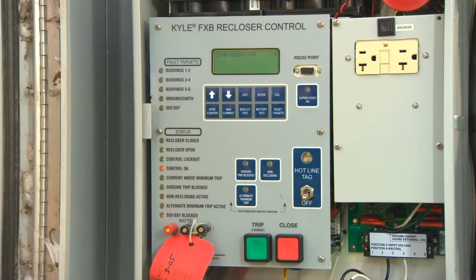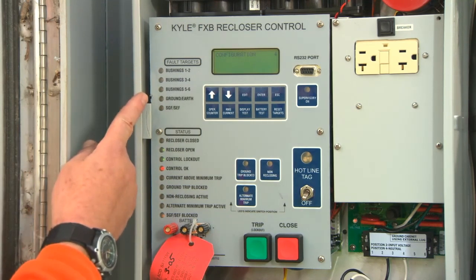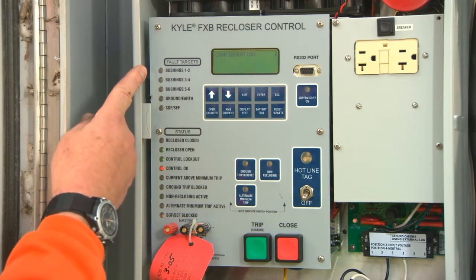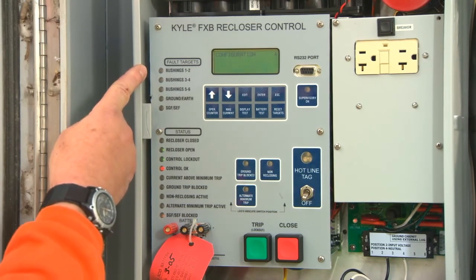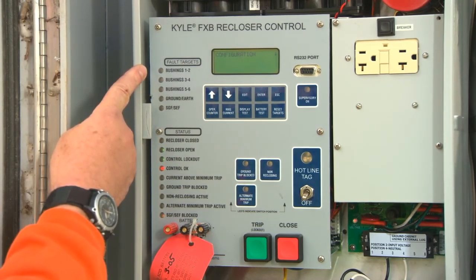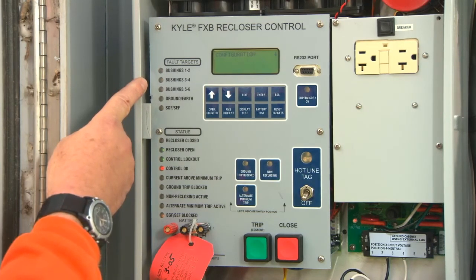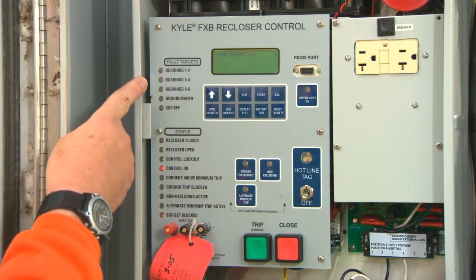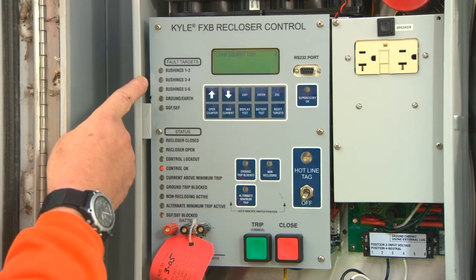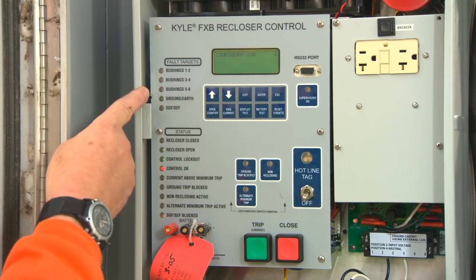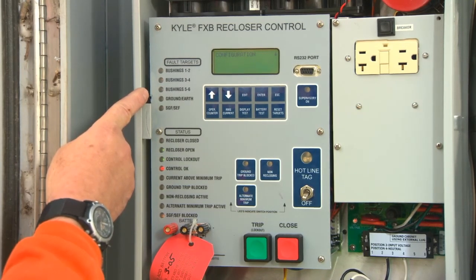Following is a basic overview of the Cooper FXB recloser control, which mates up with the Cooper WVE38 recloser. Let's start with the fault targets on the left side of the panel. Bushings 1 and 2 will be your source load, closest to the operating handle. Bushings 3 and 4 will be the center bushings, and bushings 5 and 6 will be the farthest away from the operating handle.